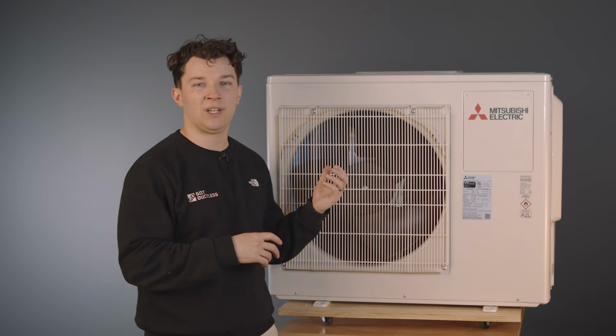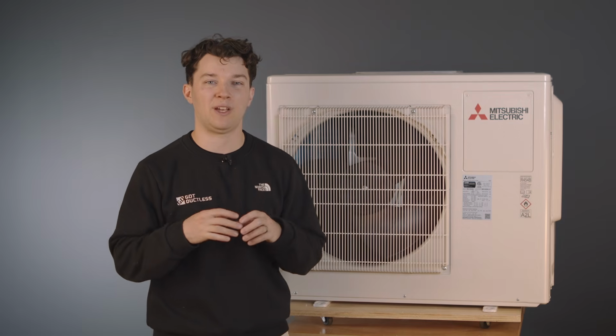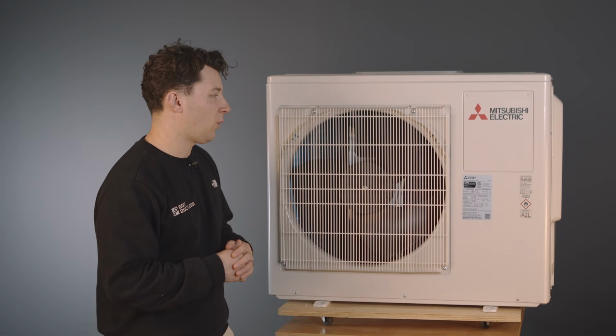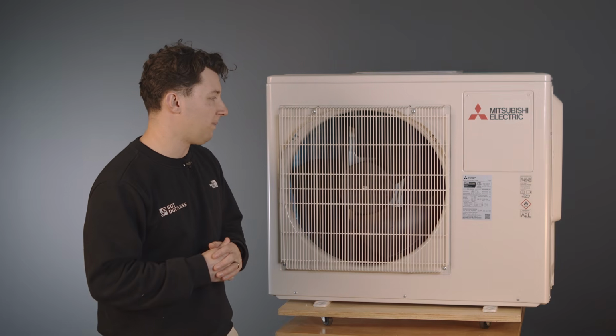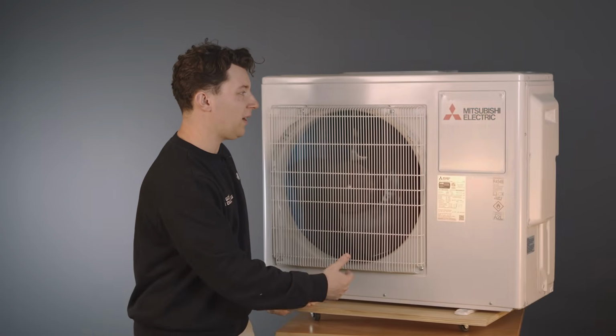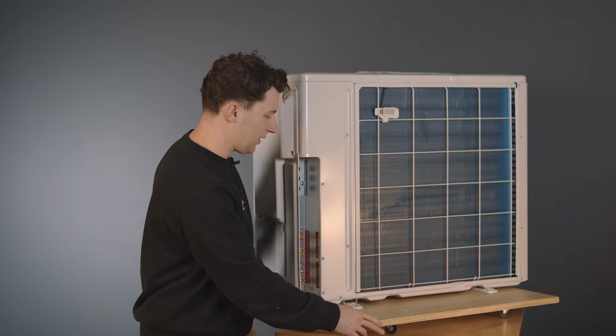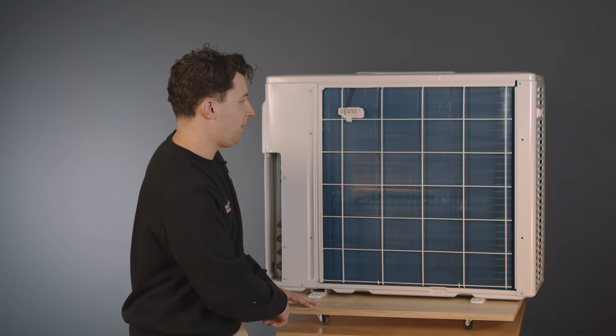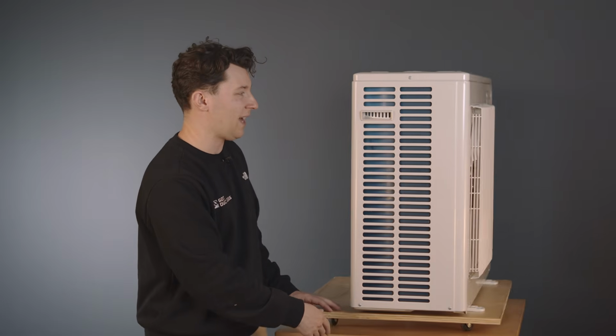So to go into some of the specifications, this outdoor unit is replacing the MXZ-2C20NA that was available in R410A, and now this MXZ-2D20NL is actually the R454B refrigerant substitute for that older 2C20NA outdoor unit. Now, Mitsubishi went with R454B because they wanted a future-proof refrigerant in case the EPA had some stricter guidelines and restrictions, and so that's why they chose this R454B for this particular series moving forward. But as you can see, it's a single fan unit. It's very compact for a two-zone system, and here, as you can see in the back, you have two sets of ports here, as well as a coil here exposed. It has a bluish tint. We'll get to that here in a little bit.